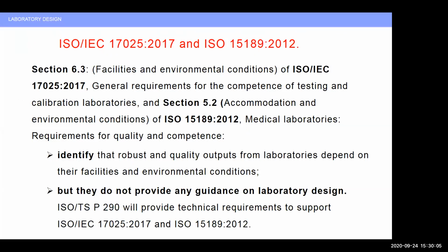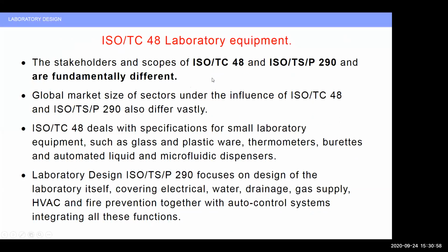Concerning the link with ISO 17025 and ISO 15189, we can read in these two documents general requirements concerning the laboratory itself. It's written that we have to identify that robust and quality outputs from laboratories depend on their facilities and environmental conditions. But those documents do not provide any guidance on laboratory design. So it's a very general requirement without giving any detail. The idea of the new proposal is to provide technical requirements to support these requirements that we can find in those two standards.